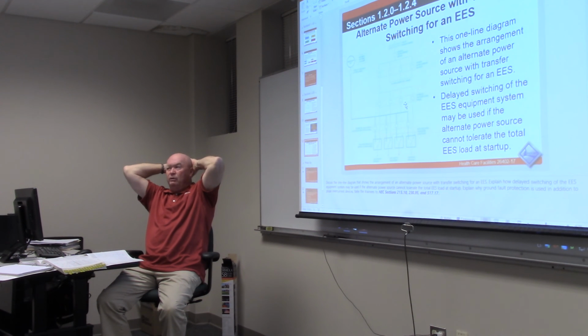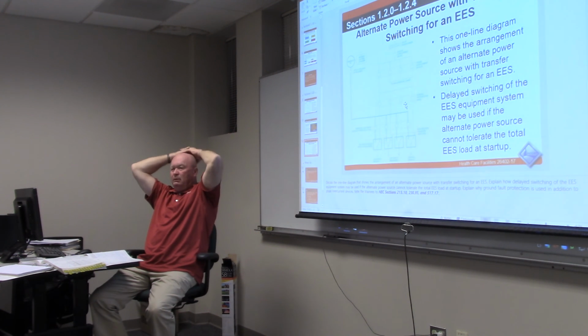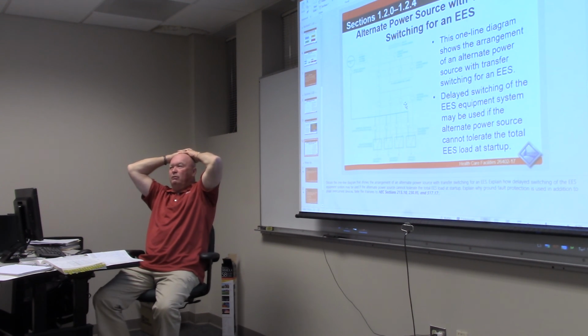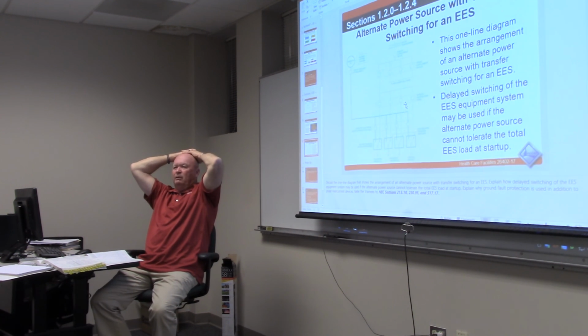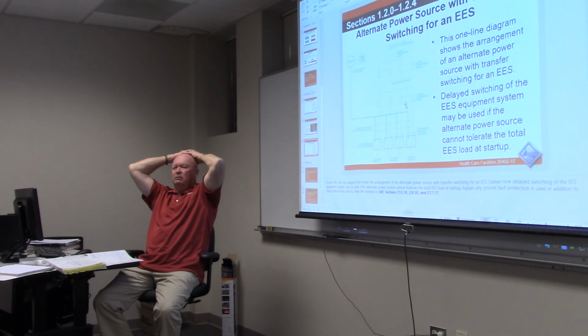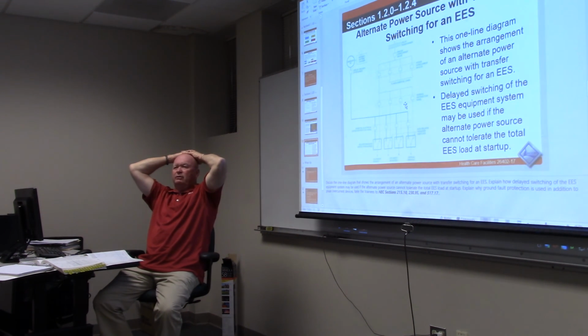In other words, with delay switching, say we have a non-critical equipment branch load inside a building—is it critical that the air conditioning work within 10 seconds? No. What's probably the largest load in the building? The AC or the heat. Say we have 2 large rooftop units—what happens when those start up? They've got motors, so they're going to surge. What if the generator can't handle the large surge of both rooftop units together?